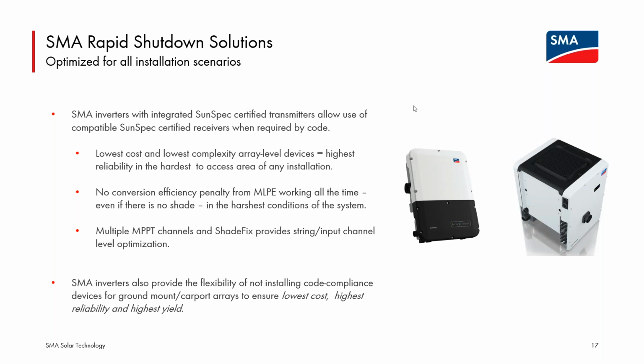They don't break the string. So in essence, they are simple on-off switches. So far less complexity, even if code is requiring them. And we showed carport installations, ground mount installations with the CORE1. Those may not be the vast majority of install scenarios, but quite often those installs may not require rapid shutdown. In that case, you simply don't use the SunSpec receivers at the array. The inverter does not need them to operate.